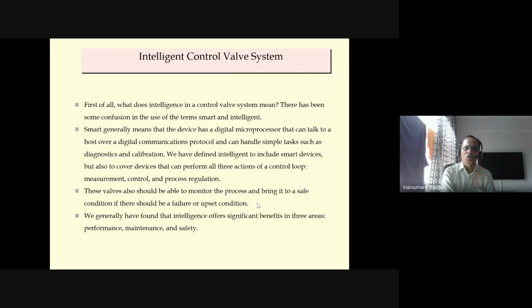We generally have found that intelligent offers a significant benefit in three areas: performance, maintenance, and safety. So when I say a valve is smart, smart means based on HART protocol. Based on fieldbus, Foundation Fieldbus or Profibus, it is an intelligent valve. And what does intelligence mean? It will measure, control, and regulate. And what does smart mean? It will do the diagnostics and online calibration. So this is what you understand now.